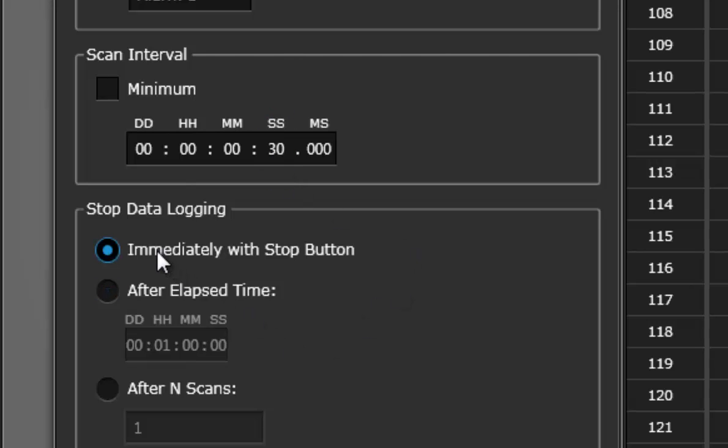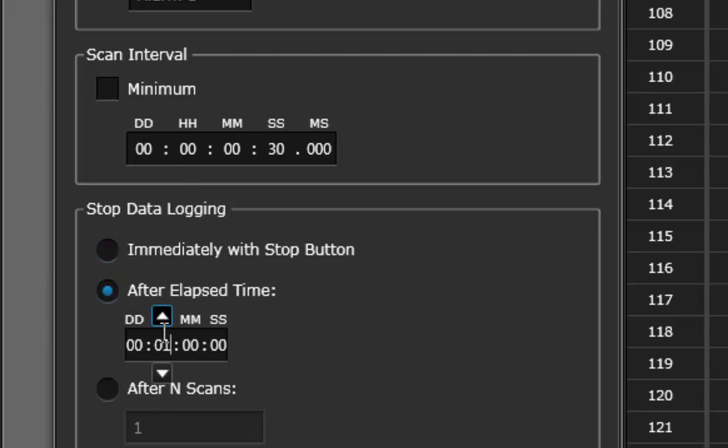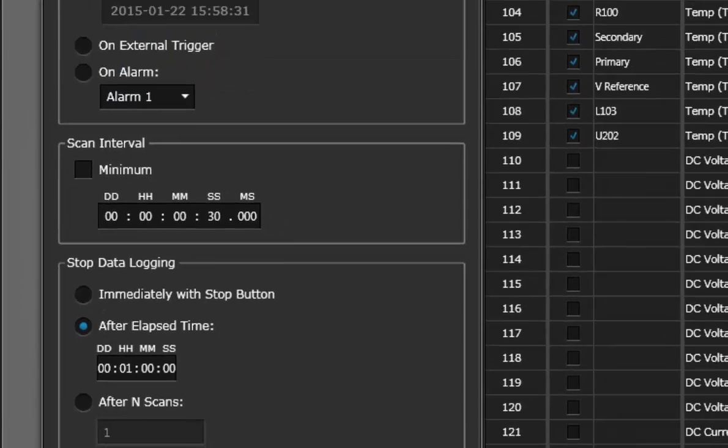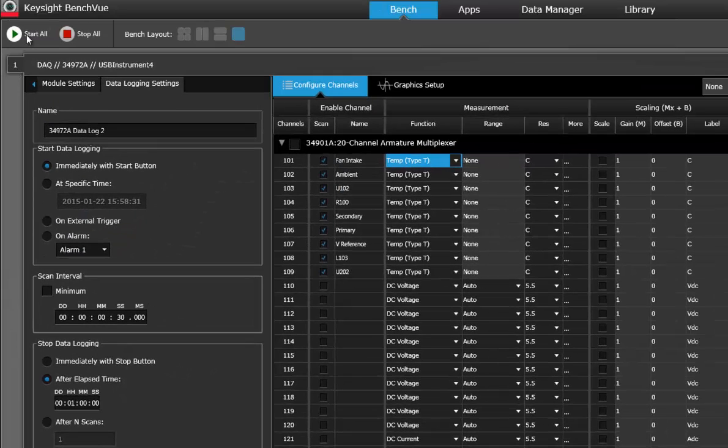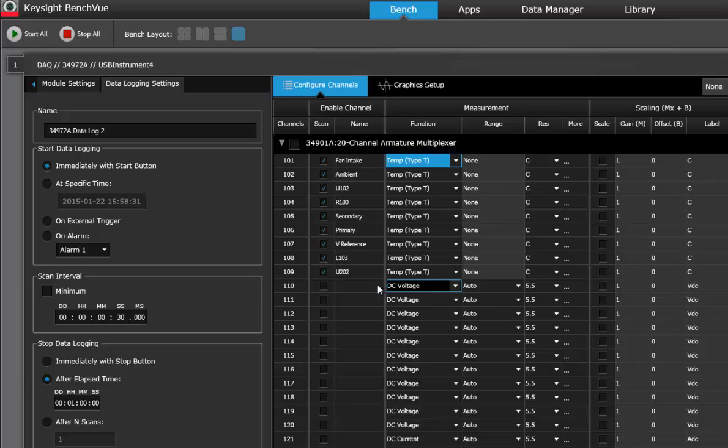And then I want to stop data logging after one hour. So what it's going to do is after I press the start button it's going to scan through all nine channels, make a measurement on each channel once every 30 seconds, and after an hour it's going to stop making those measurements.